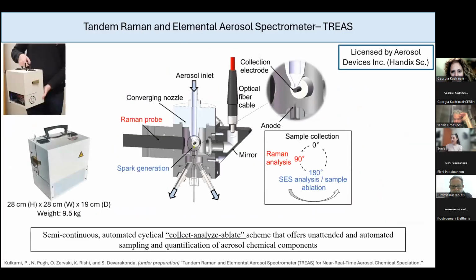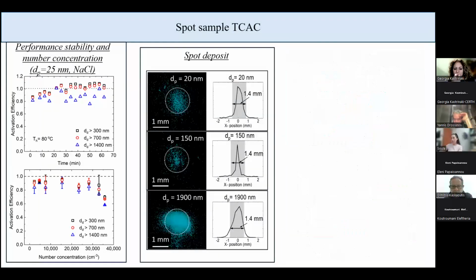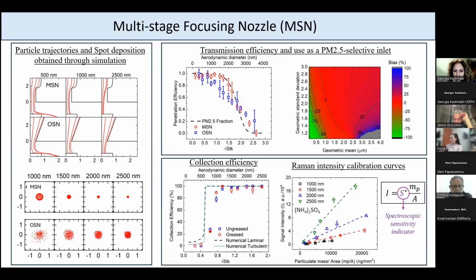Are you referring to the one with the different particle sizes? Yes. Okay, let me go there. Can you repeat your question? Yes. In this sensitivity indicator, you mentioned that the intensity of the Raman signal can be correlated to the concentration of your sample or to the size. Yes. So this is an intrinsic problem that Raman has. Generally, for any particle size distribution we have, we collect different masses, and we get the calibration curve. Because it depends on the particle size, this should always be accompanied by the particle size distribution that you have every time.